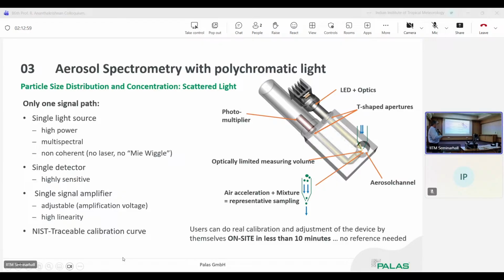But what we can do with a photomultiplier, for our systems, is measure different size ranges. Means, for example, from 0.3 to 17 micrometers, or 1 micrometer to 100 micrometers. And that's due to the fact that we amplify the signal. If we had, for example, a 100 micrometer particle in a range where the system is set for 170 nanometers up to 30 micrometers, then the signal would be much too high. Yeah, so we cannot identify that particle anymore. That's why we have to reduce the photomultiplier voltage, and then we can clearly identify those particles and differentiate them in size again. So that's the background. We tune the system with the photomultiplier to the different ranges.